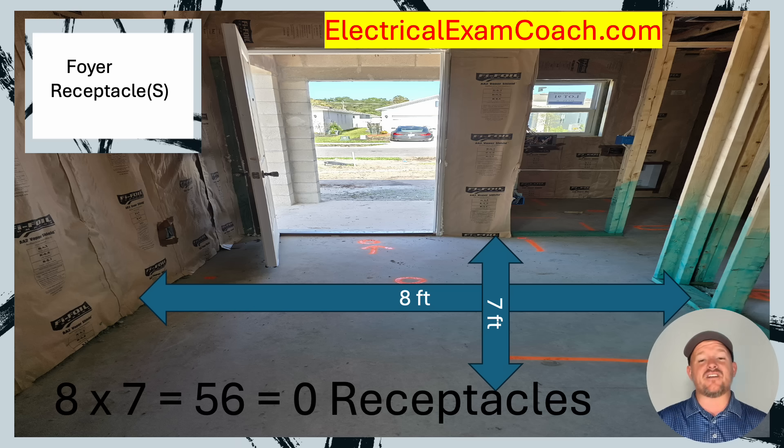Now let's imagine that it's 8 by 7. When we multiply it out, it equals 56 square feet. So we know that we might have some receptacle outlets in this foyer, if there are any walls that are 3 feet or larger. And for every one that is, there's required to be a receptacle outlet. Let's take a look at the walls.